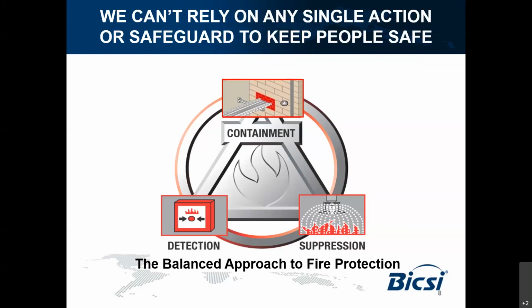Sprinkler systems are designed based upon the calculated fire area. If a fire rapidly spreads beyond the designed containment area due to improper fire stopping, for example, because a cable was forgotten or not sealed properly, additional sprinkler heads could be activated. It would dilute the intended volume of water supplied to the area of the original fire occurrence.